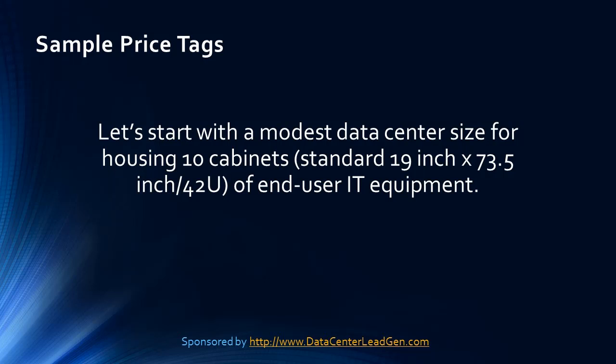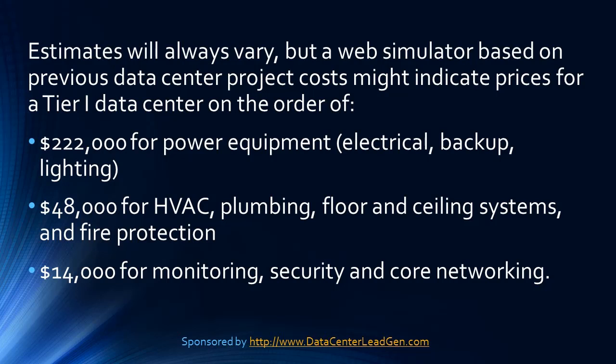Sample price tags: let's start with a modest data center sized for housing 10 cabinets — standard 19-inch by 73.5-inch, 42U of end-user IT equipment. Estimates will vary, but a web simulator based on previous data center project costs might indicate prices for a Tier 1 data center on the order of $222,000 for power equipment, electrical backup lighting; $48,000 for HVAC, plumbing, floor and ceiling systems, and fire protection.